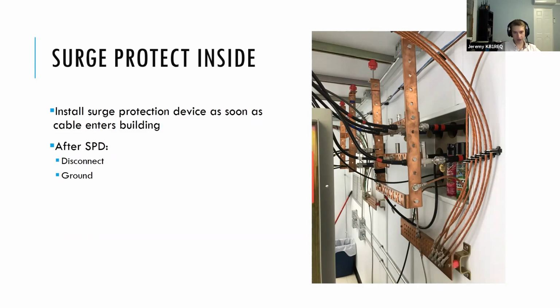And then after the surge protection, you either want to ground everything and ground it again back to a low impedance ground system with large conductors, or alternatively, if you can, disconnect. In a home station, it may be easier to disconnect right after that surge protector comes in, if you're not going to be using your station, or it's a lightning event, a high risk for a surge. That goes to our mantra of isolating your equipment from the surge. Everything's still grounded at the surge protector, but you take the equipment out of the equation essentially.